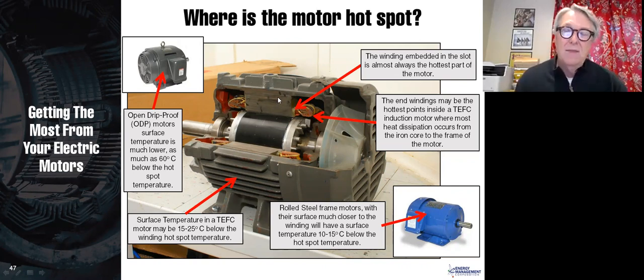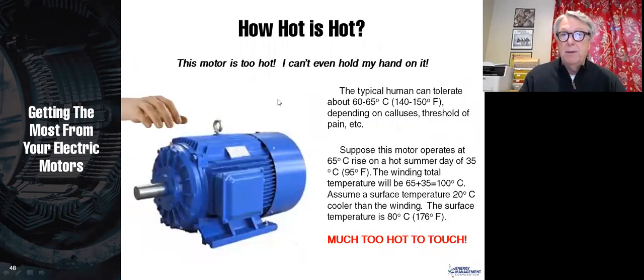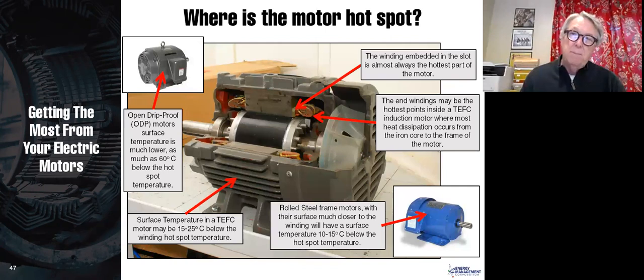But you can't get in there with an infrared thermometer or a thermography device. And so where are you going to measure it? You want to measure it generally in the middle of the motor right here, right over that iron. That's probably the best place to measure that motor temperature. And that's going to give you more of an average temperature. And again, on a TEFC motor, you want to add 25 degrees to that in order to give you a good guess on what the slot temperature is.